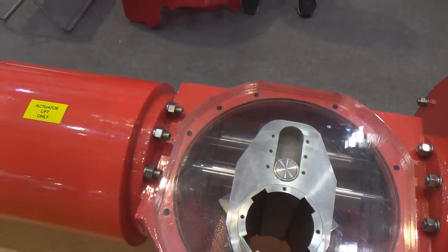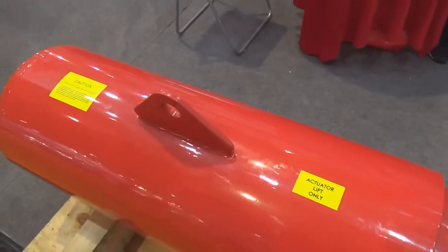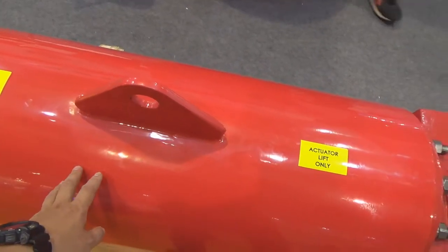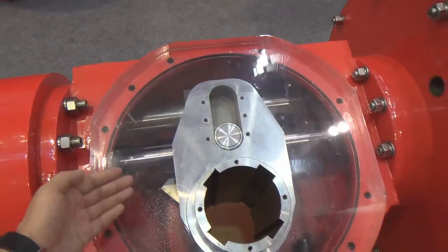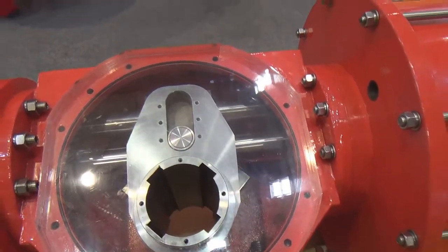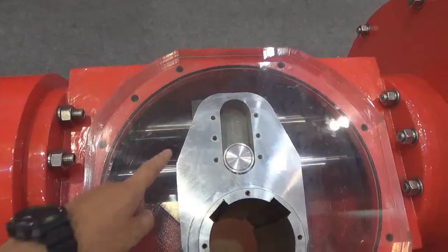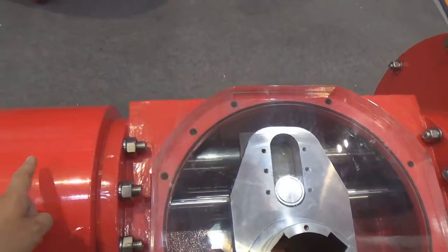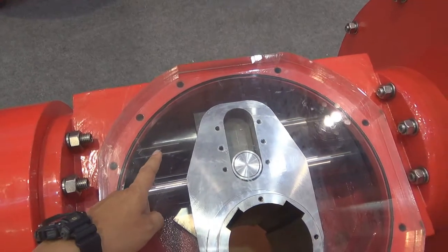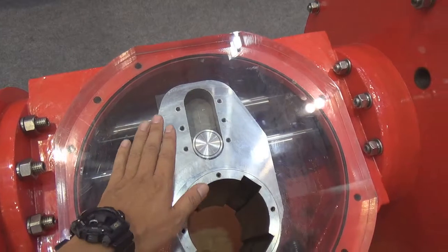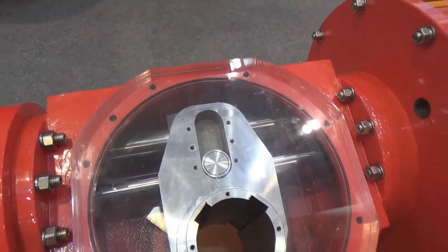valve. And when the cylinder loses the gas, inside this cylinder is a very big spring. The spring will push the downside rod and put the yoke back, so the valve will turn to the other position. The upside rod is not connected with any piston or spring. The upside rod just keeps the yoke firm and stable. So that rod is not going to work.